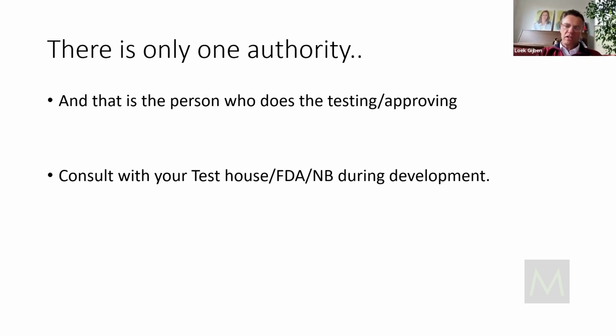So my advice is always, if you start developing a medical product, medical device, from day one, get a voucher for some hours of consulting from your test house and from your notified body. The test house cannot advise you how to do things, but what you can do is go to the test house, say what your proposal is, what you want to do, and ask, is this acceptable to you? And get it in black and white back on the mail. So then you can say it's acceptable to you for the test house, and you can go on. What we have done is, at TMSI, we did the first thing wrong. We had a totally finished product, went to the test house, and they said it's not acceptable. Then we had to redesign a finished product. Then the housing was already injection molded and bought in 100,000 parts.